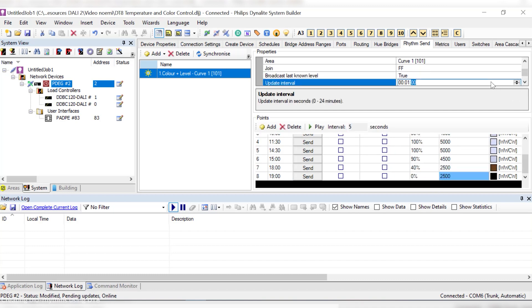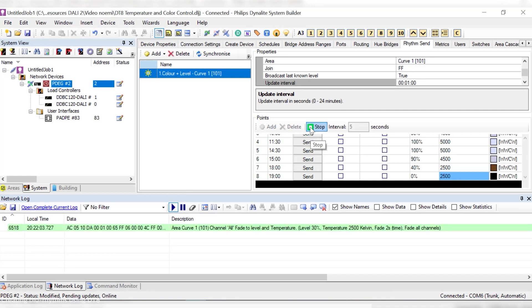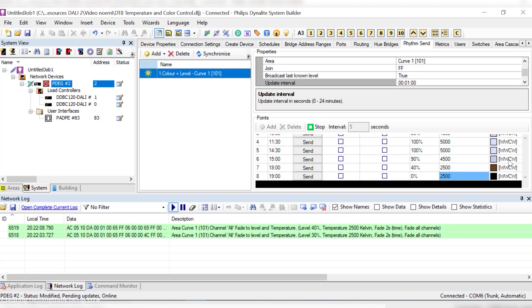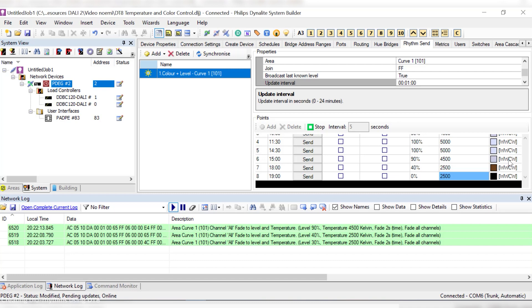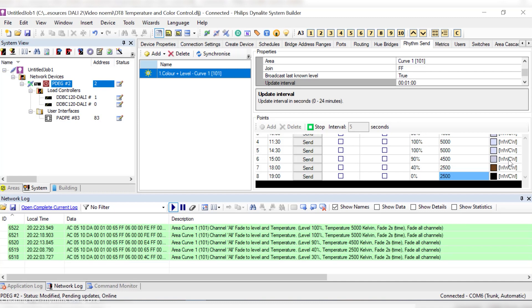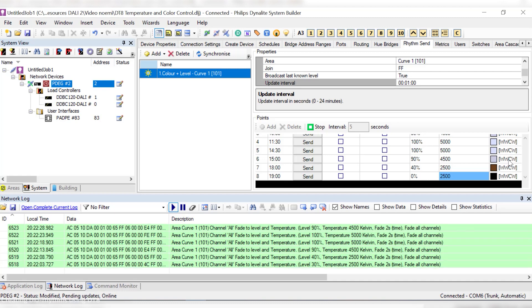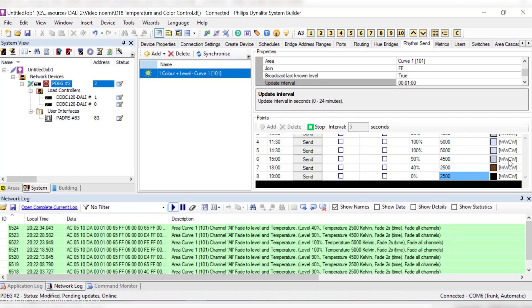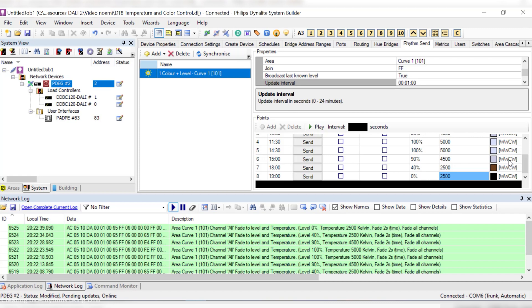By default, the curve will update every minute, but if required, it's possible to adjust this setting. Once the curve is created, we can simulate it to see if we are happy with it. By default, every 5 seconds, we will see a new Dynet2 message sent by the Ethernet Gateway. Its message corresponds to one of the points of the curve. Note that between the last point of a day and the first one of the next day, the curve will wrap around, meaning that it will keep sending levels to make the smooth transition to the first level. This behavior will become configurable in a future release, to be able to stop sending levels once the last point is reached. When we are happy with our curve, we can export it and use it in future projects by importing it.